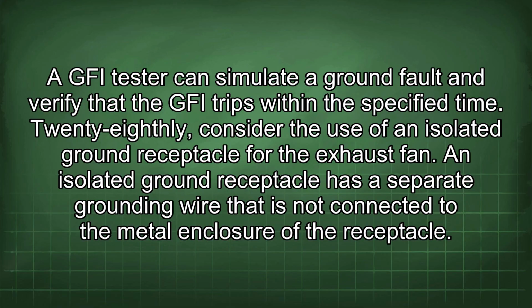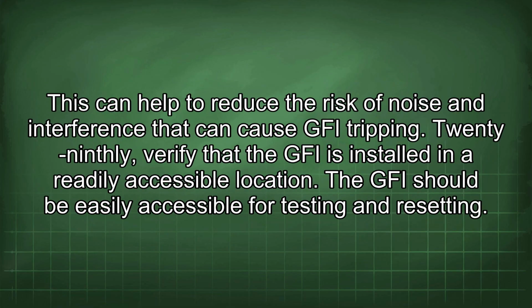28thly, consider the use of an isolated ground receptacle for the exhaust fan. An isolated ground receptacle has a separate grounding wire that is not connected to the metal enclosure of the receptacle. This can help to reduce the risk of noise and interference that can cause GFI tripping.